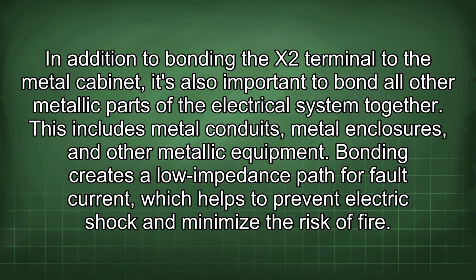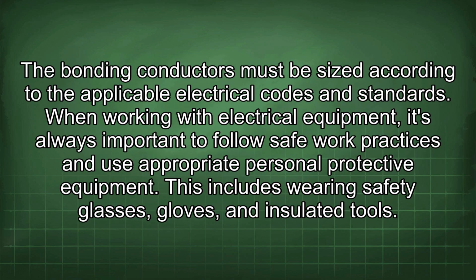In addition to bonding the X2 terminal to the metal cabinet, it's also important to bond all other metallic parts of the electrical system together. This includes metal conduits, metal enclosures, and other metallic equipment. Bonding creates a low impedance path for fault current, which helps to prevent electric shock and minimize the risk of fire. The bonding conductors must be sized according to the applicable electrical codes and standards.